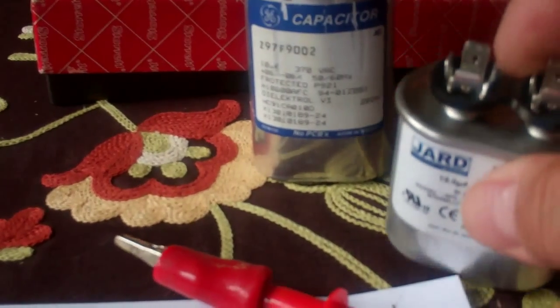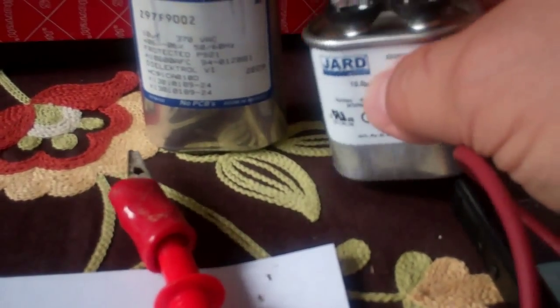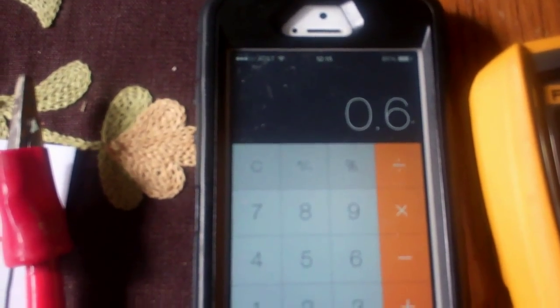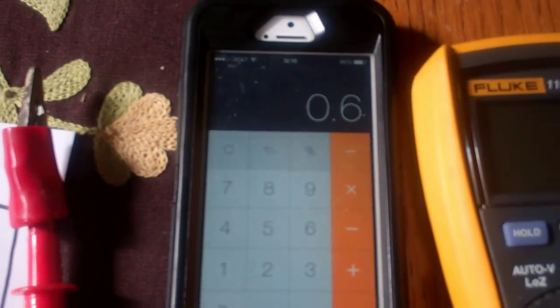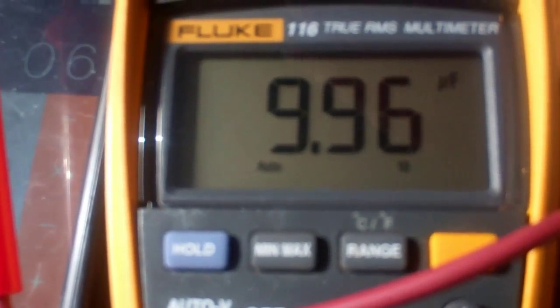So your meter should indicate 10 microfarad, plus or minus 6. So let's quickly determine 6%. 6% of 10 is 0.6. So we want to be between 9.4 and 10.6. And I turn this to capacitance. I'm getting 9.96, which is real close to 10 anyway, and it's well within the tolerances of 6%. So the capacitor is good.